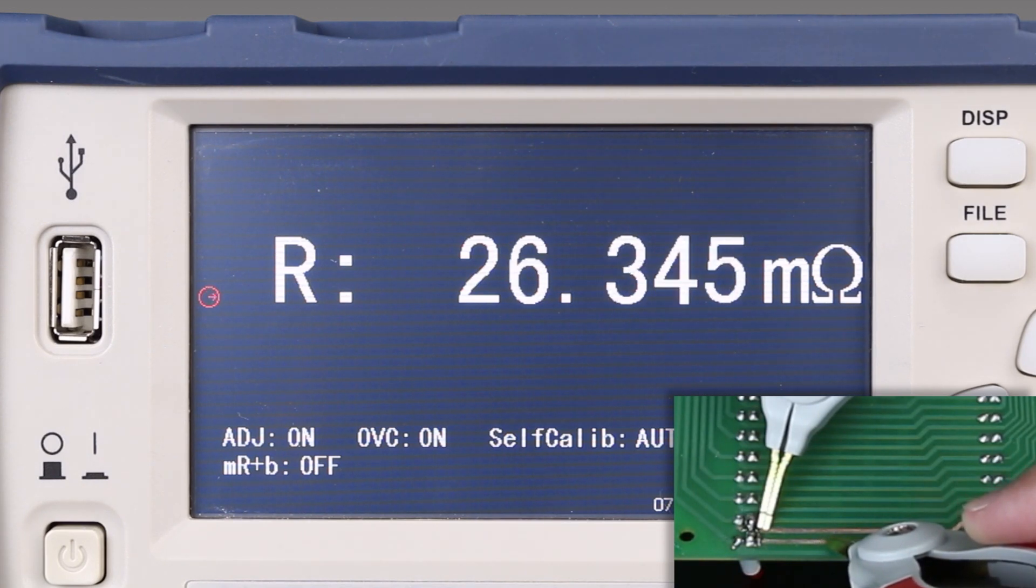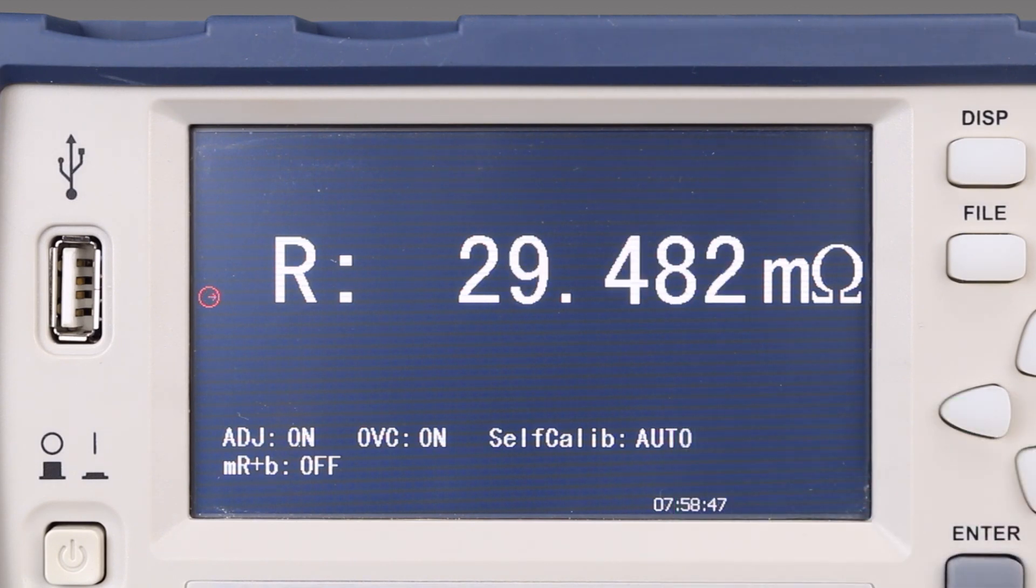Moving the test lead, we see the resistance increasing. This indicates we're moving farther away from the short.